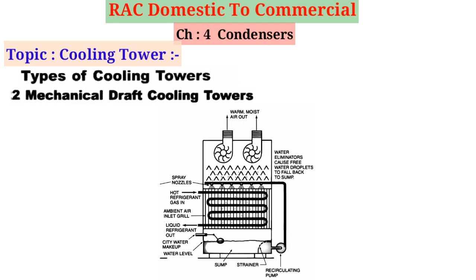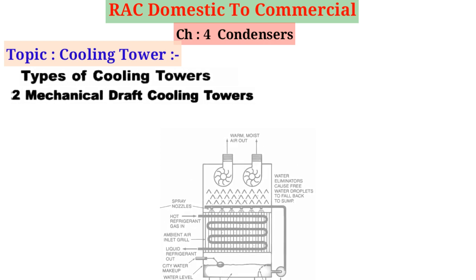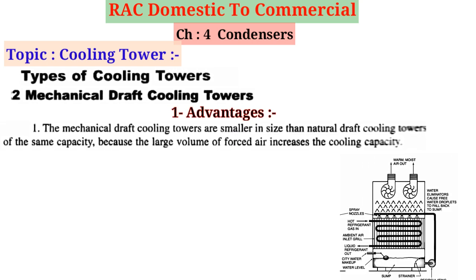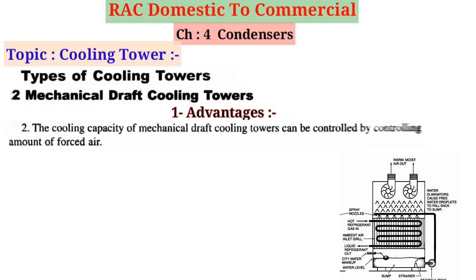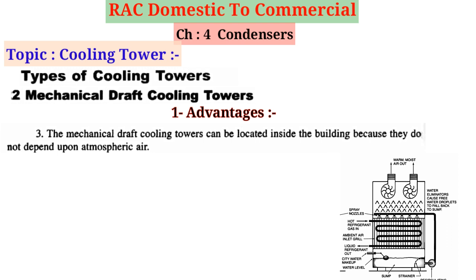Mechanical draft cooling towers are similar to atmospheric natural draft cooling towers except that fans are used to force air through them. These towers may use either propeller or centrifugal fans. The main advantages over natural draft towers are: 1. They are smaller in size for the same capacity because the large volume of forced air increases cooling capacity. 2. The cooling capacity can be controlled by controlling the amount of forced air. 3. They can be located inside a building because they do not depend upon atmospheric air circulation.